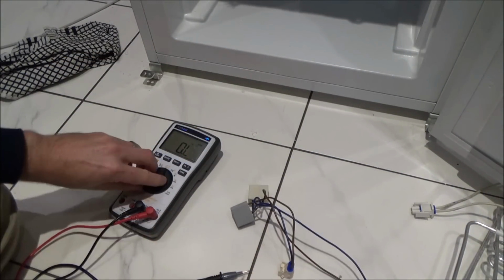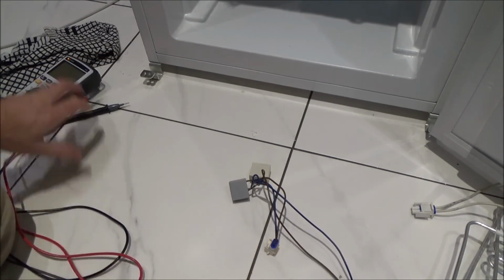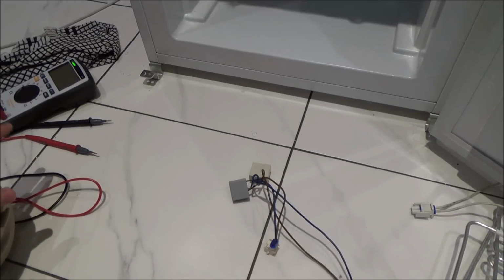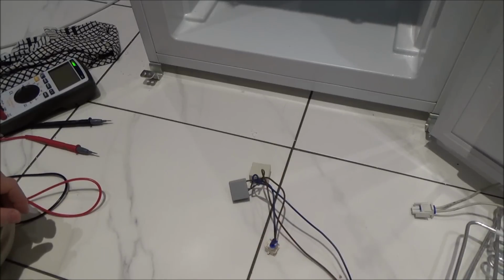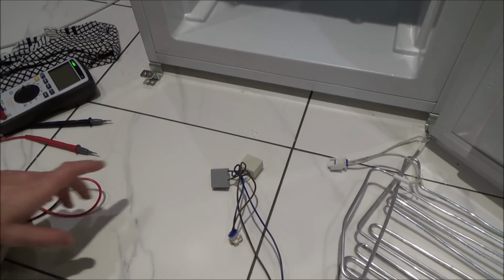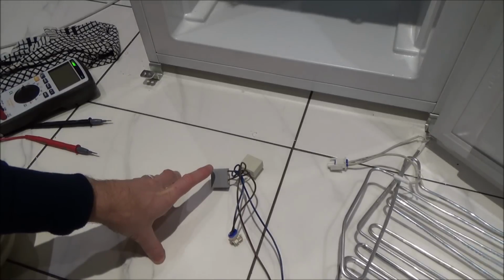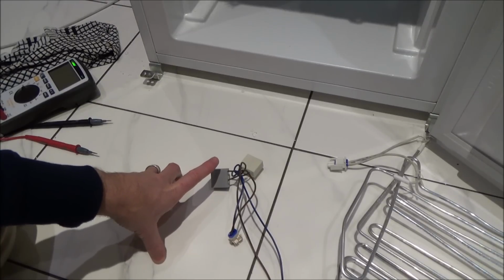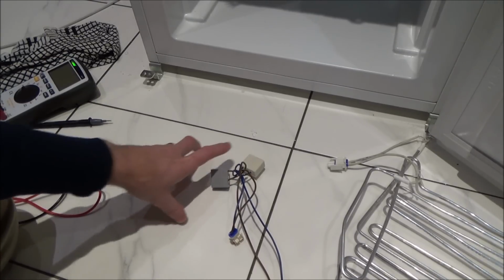So basically these are the defrost thermal cutout and also the safety thermal cutout. I think when the heater comes on, it's this thing that tells it to come on, and then this thing that tells it to go off, or something similar. Actually it must be that one of them tells it when it reaches a certain temperature, and maybe if it exceeds a certain temperature the other one kicks in.